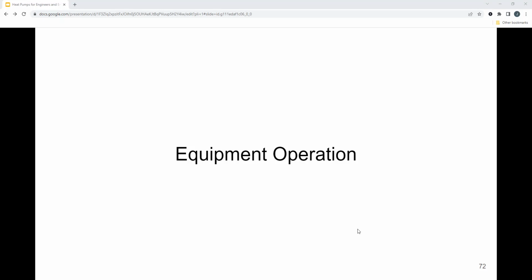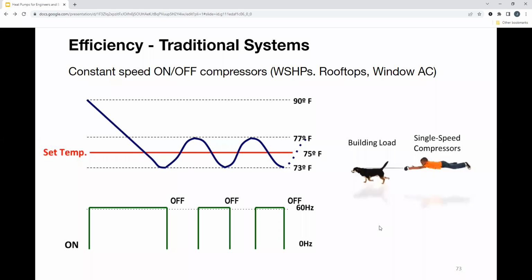So getting into equipment operation now. For those of you who've joined these presentations in the past, you've probably seen this slide, but this is very important when we are talking about equipment operation and what the differences are between traditional systems and your variable refrigerant flow systems, right? So looking at these charts, we're talking about your constant speed on-off compressors, right? So what equipment uses that? It's your water source heat pumps, your rooftop units, and your window ACs, those window shakers. All those are kind of on-off: get to your temperature and then turn off.